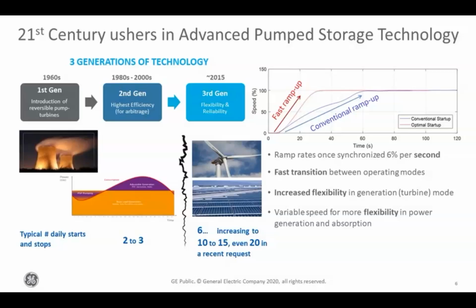We're also making machines more reactive and flexible, with increased ramp rates and faster transition times—for example, going from pumping or power absorption to full generation. We can now do that in less than a minute, from minus 150 megawatts to plus 150 megawatts. Equally, we can start a machine from standstill and reach 100% power in less than a minute.